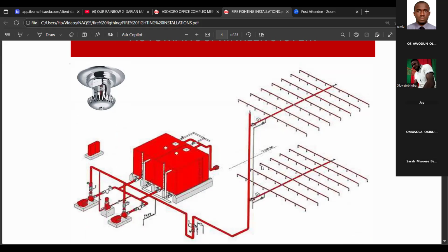Now, what are the equipment you must have? A rough list: you have your pump. From your pump, you have your air valve. Air valve is different from landing valve. The reason we have an air valve is for when there's air in your pressure line. Before your pipe is put on pressure, you must be able to release that air. It's just like a nurse who wants to give an injection to a patient. If there's air in the syringe, it's very dangerous. You have to remove the air in the line before you pump. So you must have your air valve.